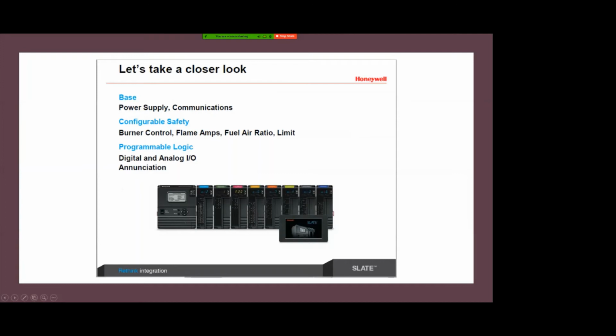Let's take a closer look at the hardware, really get into the bones of this thing. We have the base unit, the module all the way to the left, about 2.5 times the size of all the other modules - that's the base unit. That's where the power supply resides, as well as the communication ports. The communication ports native to this base module are Modbus and BACnet, very much industry standards not only in the industrial space but the commercial space. We can easily tie this system back up into an overall building management system and pull any and all data out of this base unit relative to the system.